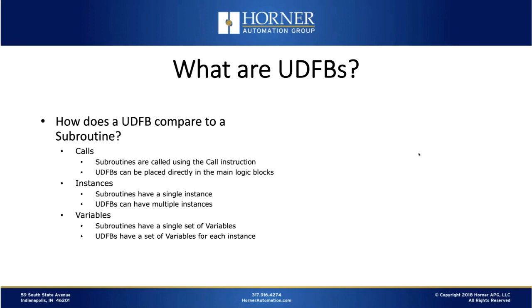User-defined function blocks, however, can be placed directly in the main logic blocks scattered throughout your program. User-defined function blocks have multiple instances. Subroutines, again, only have a single instance with a single set of variables, no matter how many times you call it. Whereas UDFBs have a unique set of variables for each instance. That's probably the biggest difference between the two. They're both important tools for having well-organized and reusable code.